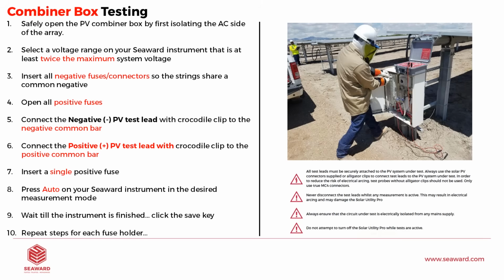The second thing we're going to do, we're going to open up all of the positive fuses. Okay, so we're going to open up all of those positive fuse harnesses. Now, the very best practice that I advise is to take out all of the fuses from those harnesses and put them to one side. Then take one single fuse, and we're going to use that for later. What we're then going to do is we're going to take our Solar Utility Pro, and we're going to connect one alligator clip to the common negative and one to the common positive. Now, bear in mind, right now, we don't have any string connected because none of the positive fuses are inserted or indeed inside the harness.